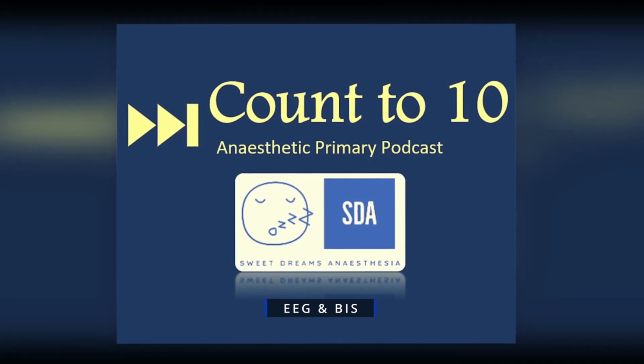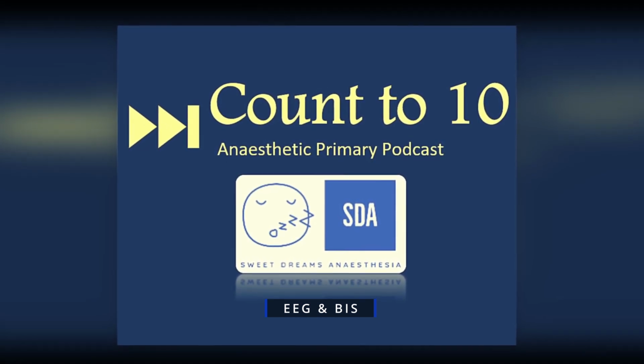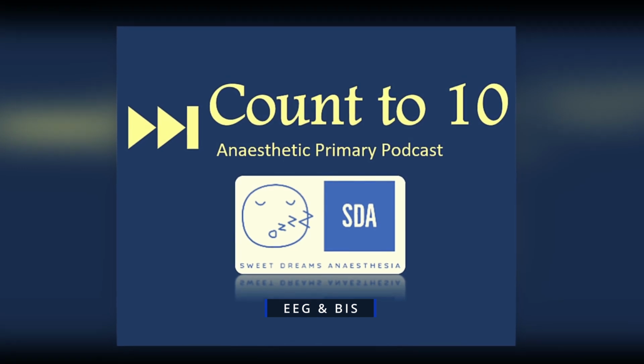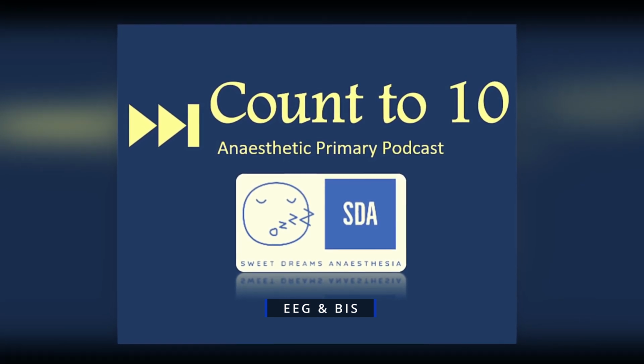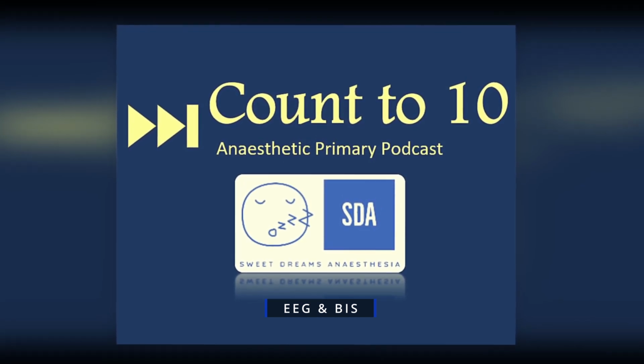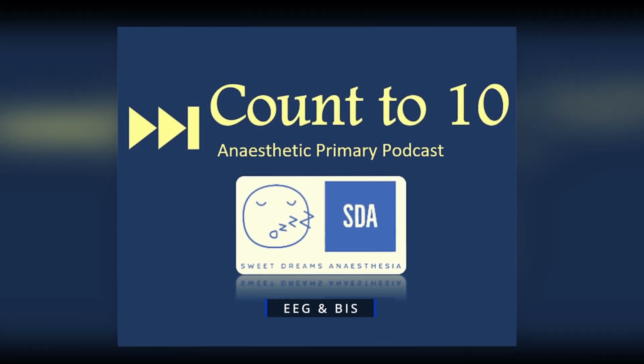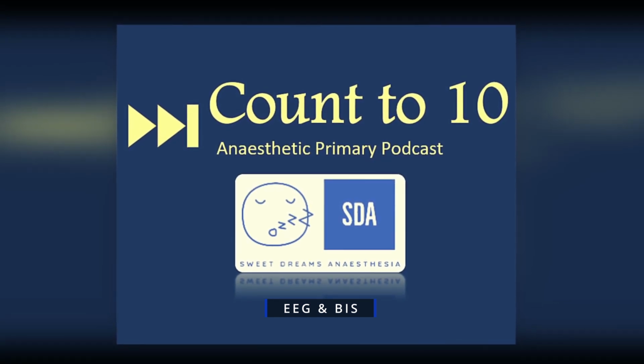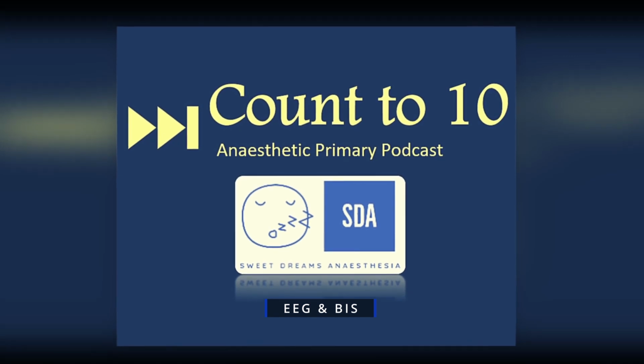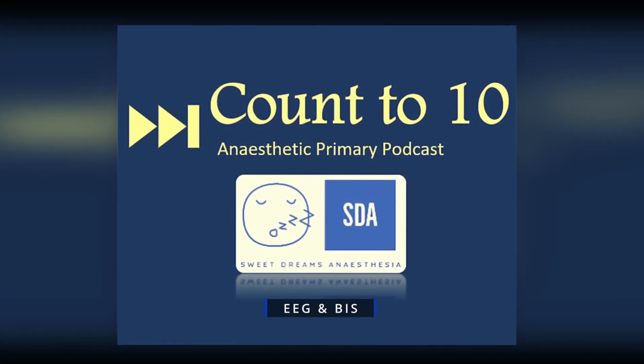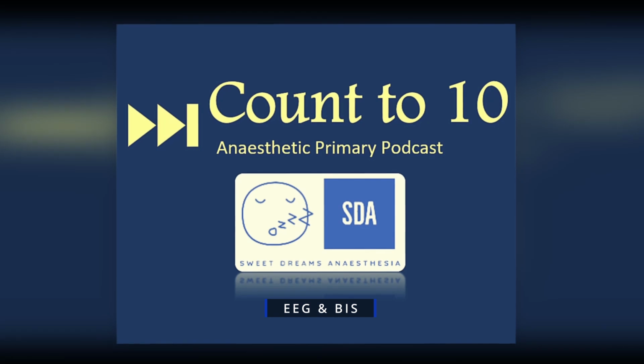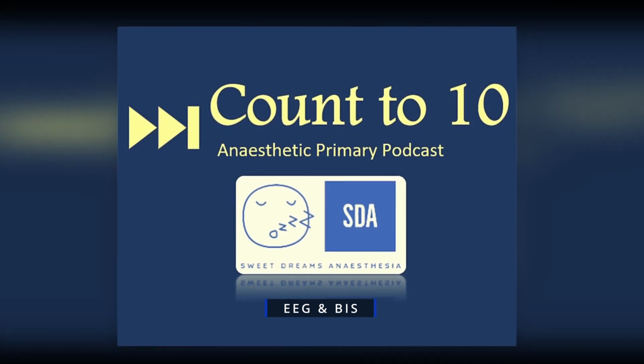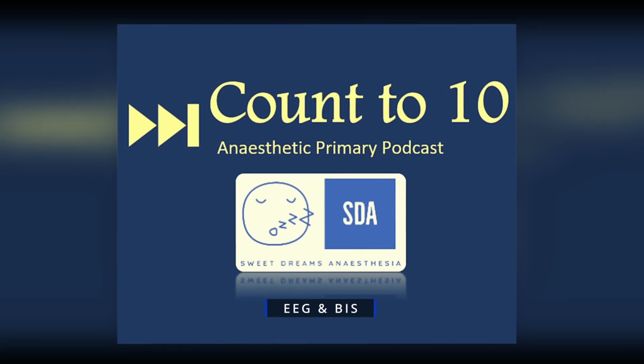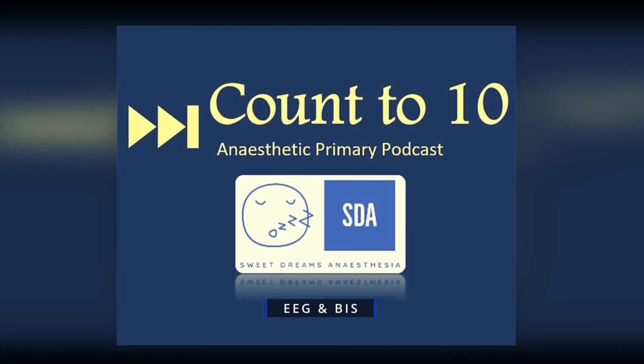It's generated by looking at the specific neurons which are within the superficial layers of your pyramidal cells in the cerebral cortex, both generating those inhibitory and excitatory postsynaptic potentials. These tiny electrical potentials are modified by bone and soft tissue of the head before they are recorded by scalp electrodes, then processed by low and high frequency filters and displayed on an 8 or a 16 channel EEG waveform.